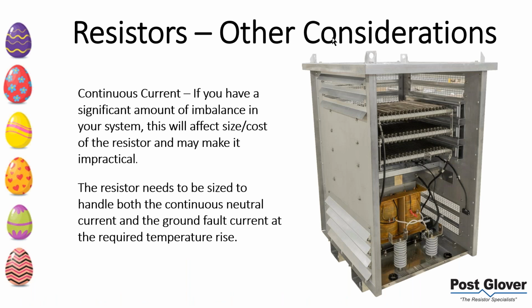Other considerations as well. A lot of times when you have larger systems with larger voltages, you see a certain percentage of imbalance. For a 5 kV transformer, that's going to be extremely small. If you're talking about a huge transformer, over 15 kV with a large service, 1200 amps, whatever it's going to be, the potential for imbalance can be greater. So you need to worry about that as well. It's another consideration you need to worry about.